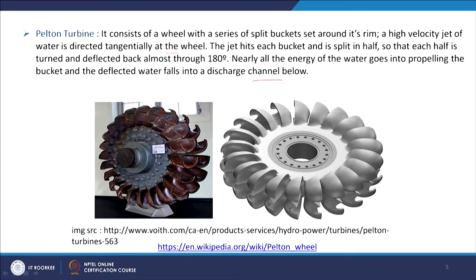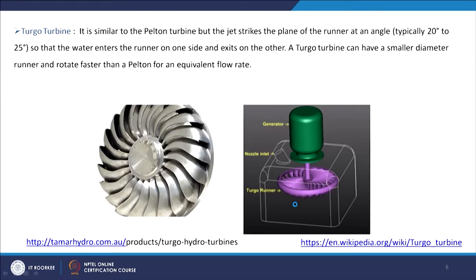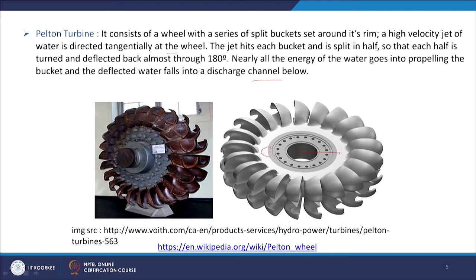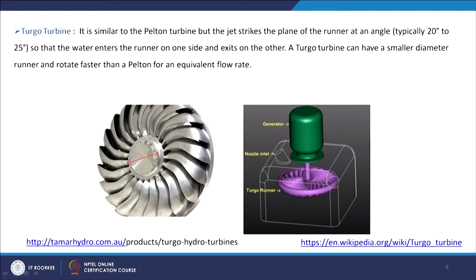Another type of impulse turbine is the Turgo turbine, similar to the Pelton but with different design. The diameter is smaller, and the jet strikes the plane of the runner at an angle — typically 20 to 25 degrees — so water enters the runner on one side and exits on the other. The Turgo turbine can have a smaller diameter runner and rotate faster than a Pelton turbine.